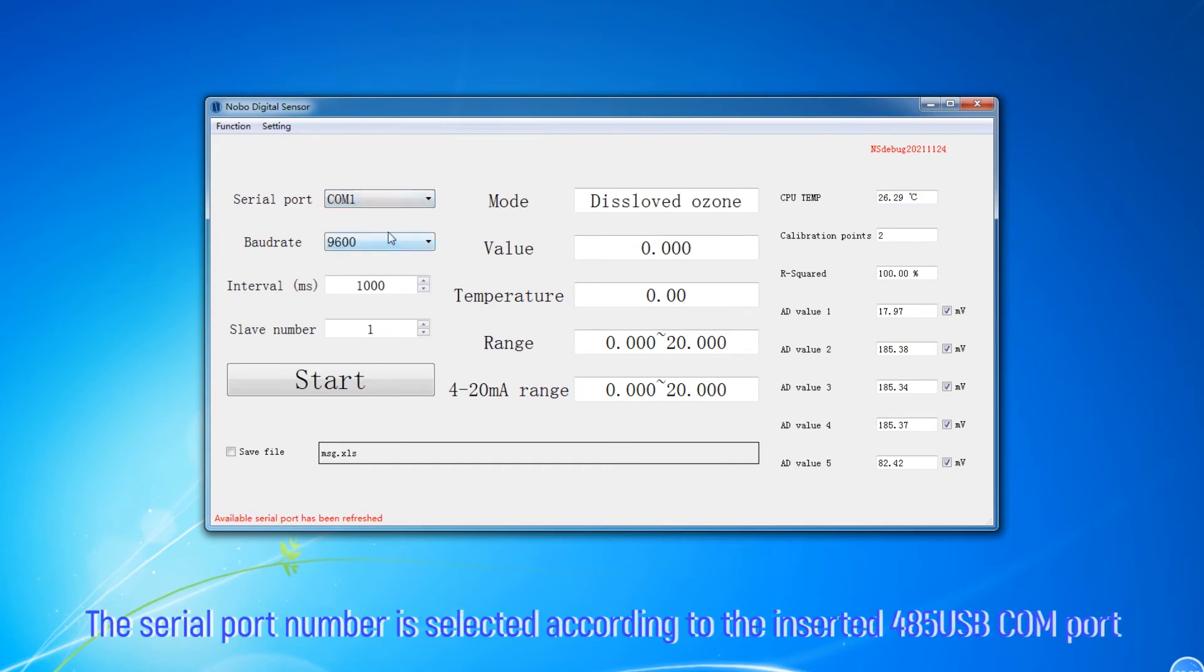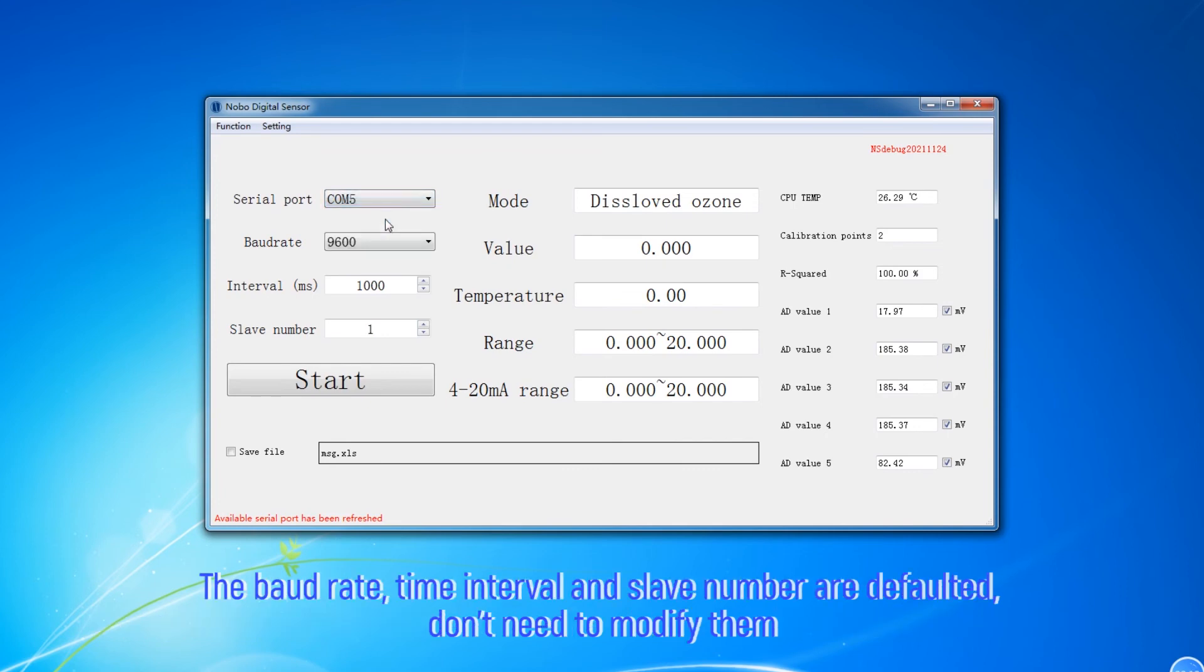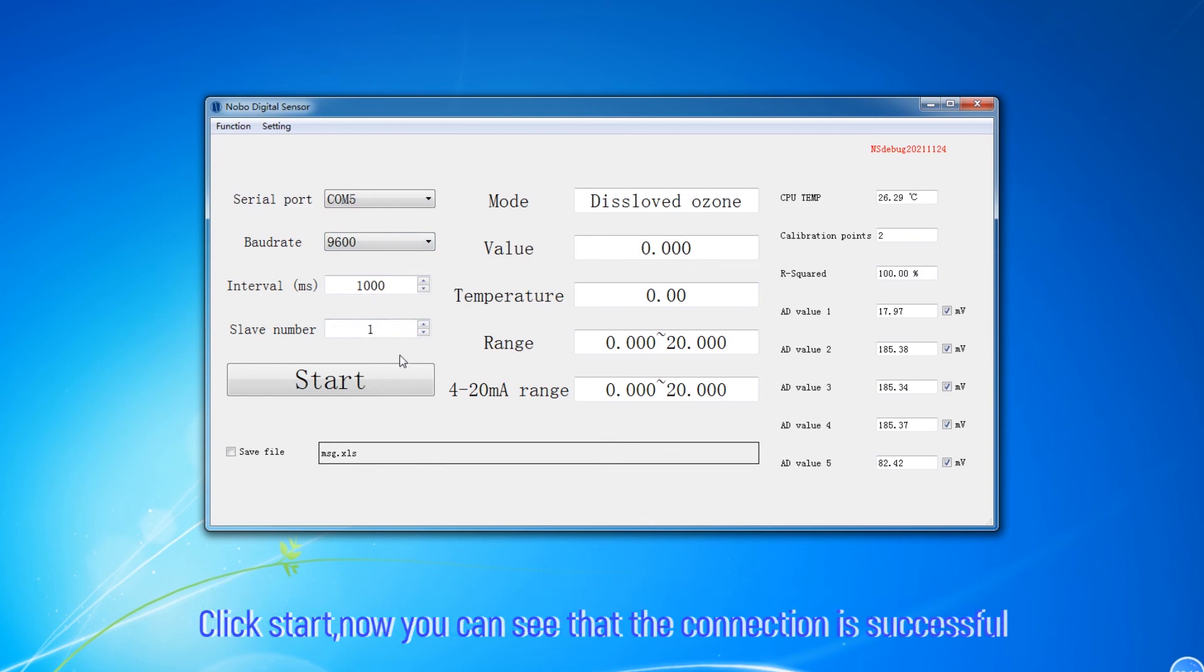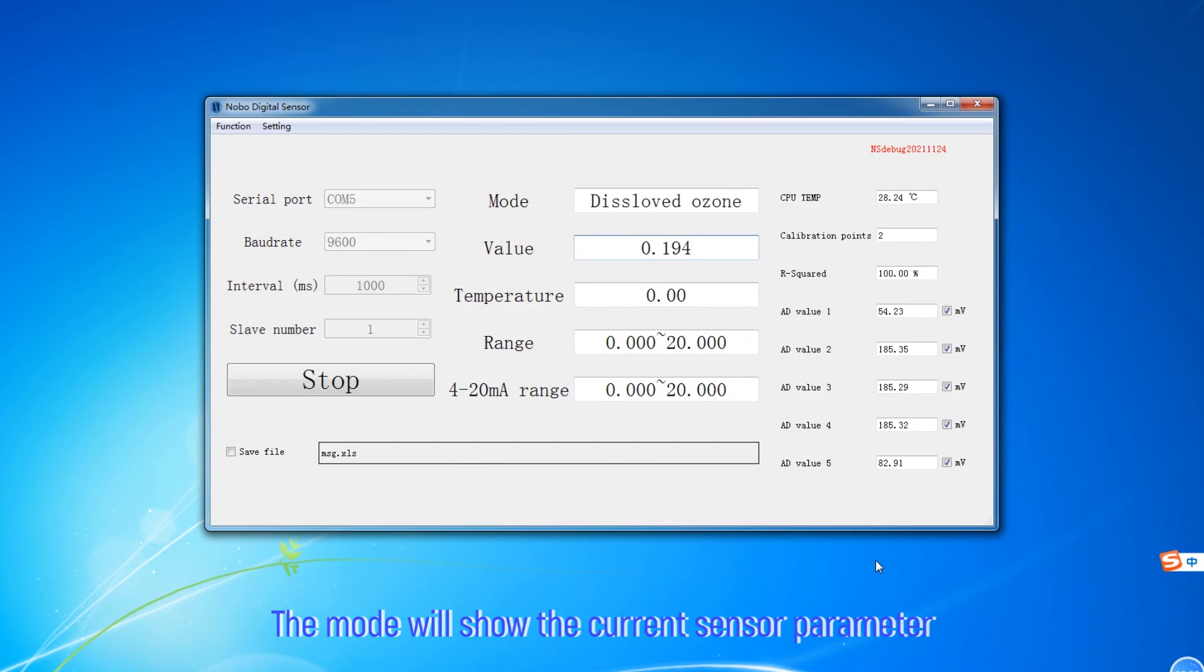Serial port number is selected according to the inserted 485 USB COM port. The baud rate, time interval, and slave number are defaulted and don't need to be modified. Click Start. Now you can see that the connection is successful and the mode will show the current sensor parameter.